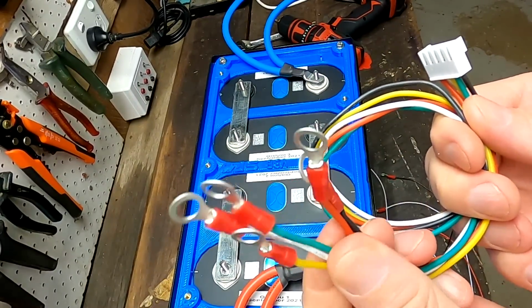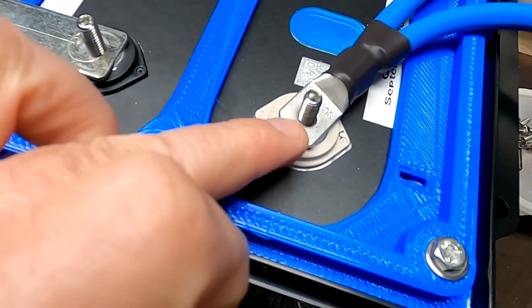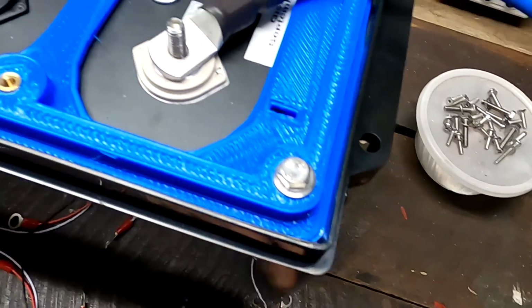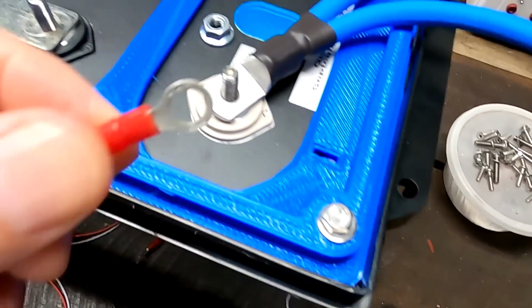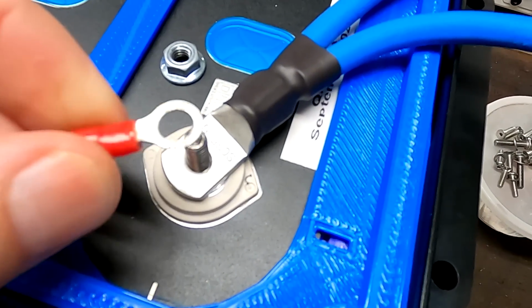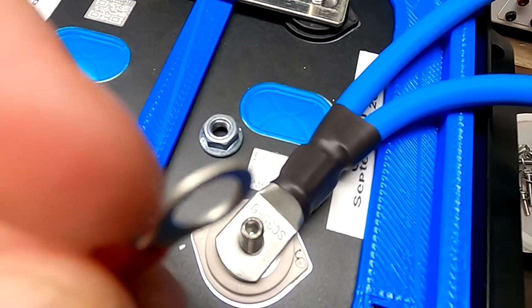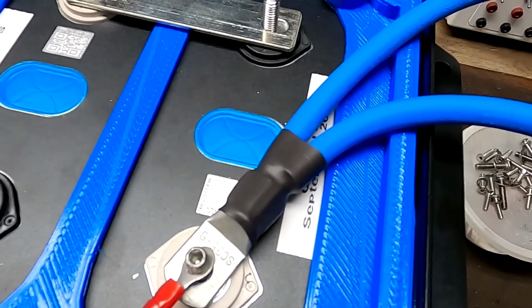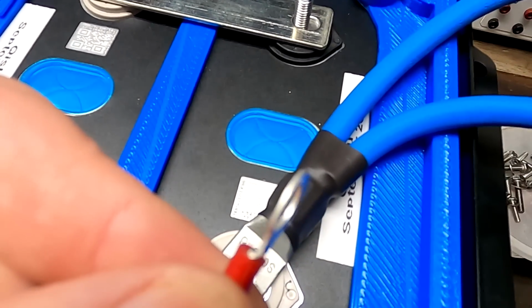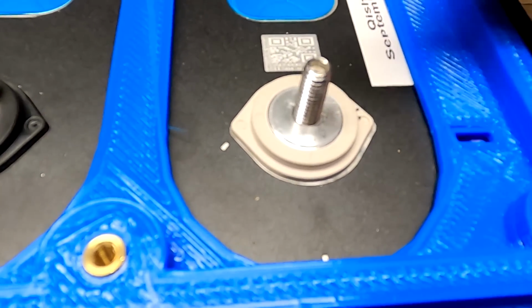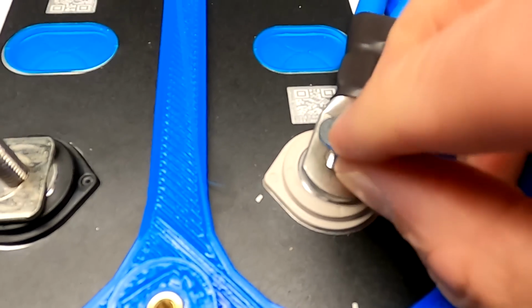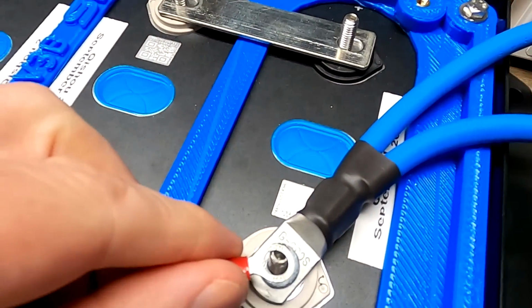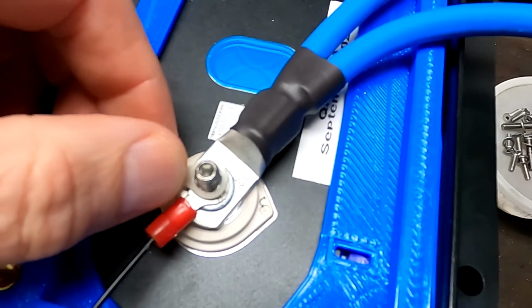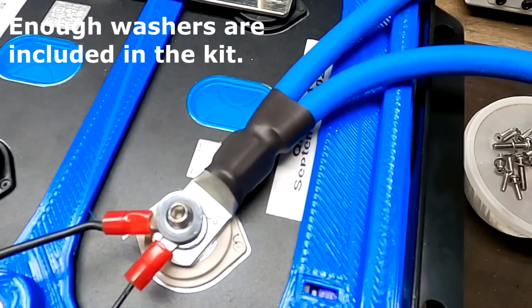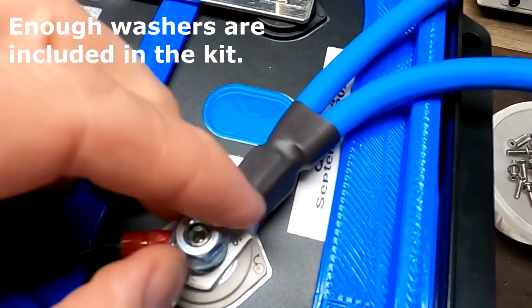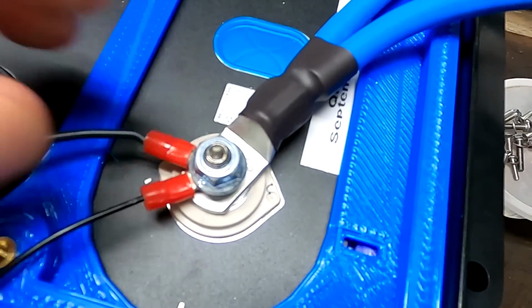Because we are using these flange nuts to tighten our terminals, the manual says to have washers underneath and above our balance cables for the BMS and active balancer. I quite like this information, because see these tiny ring lugs? When you tighten the flange nut, it will actually bite into the material of the ring lug, and they are not very thick. Of course, there's no washer underneath the main cable, then a washer, balance cable for the BMS, balance cable for the active balancer, another washer, and our flange nut. This is exactly as I would have done it as well. Nice job.